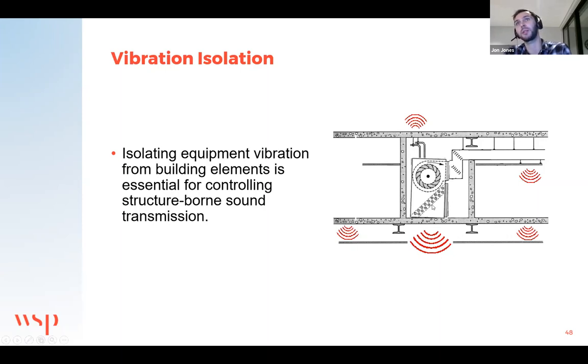It's not just the equipment itself we need to consider, though, but I think if we click through, it's also everything that's connected to the equipment. So here, if you've got pipework or ductwork connected to a fan, this is also going to be moving with the equipment, and any vibration levels that might be in those need to be controlled as well.